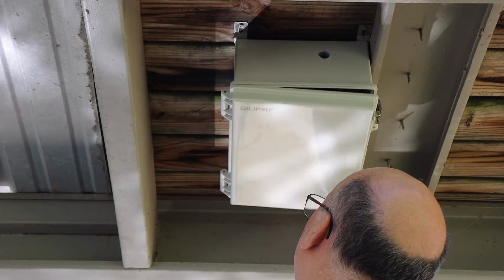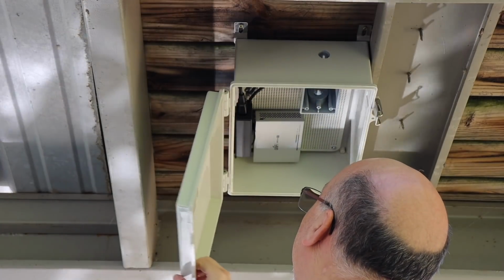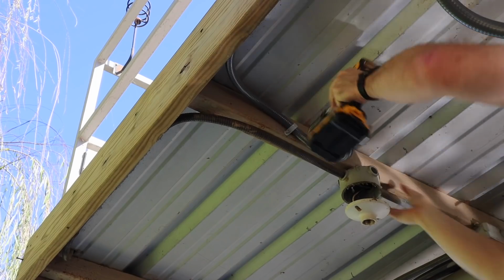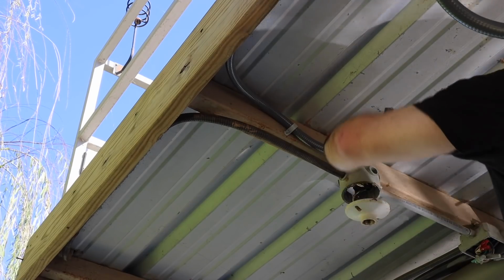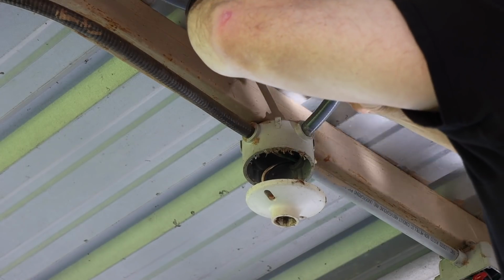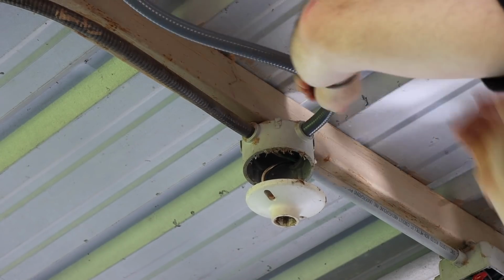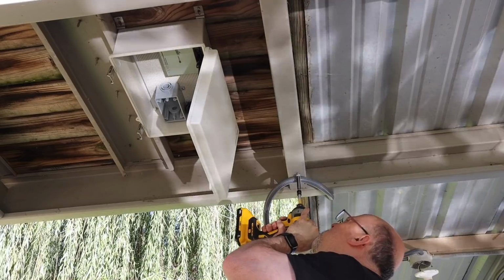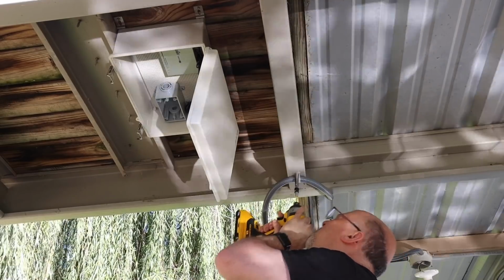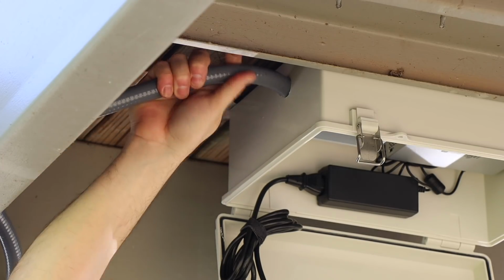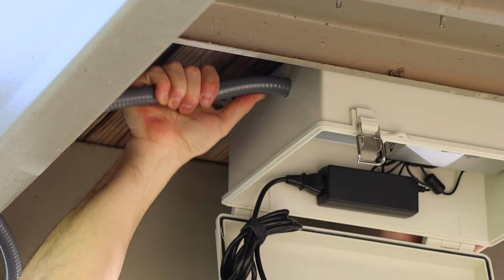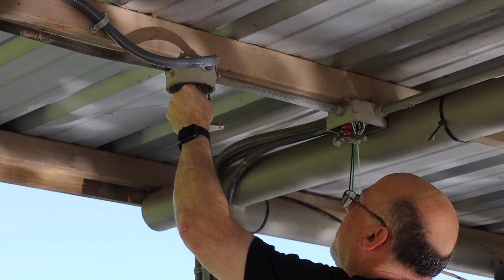Next up, we need to get electrical over here. I pulled power from an existing box that powered the lights and outlets around the dock, routing it to the new box through flexible watertight conduit. Every 18 inches or so, I strapped the conduit to the deck railing. I then installed the other end of the conduit into the electrical outlet, using glue and water sealer at both ends.